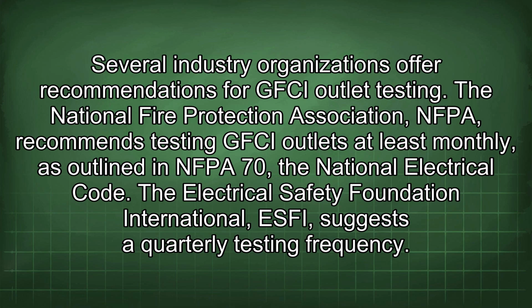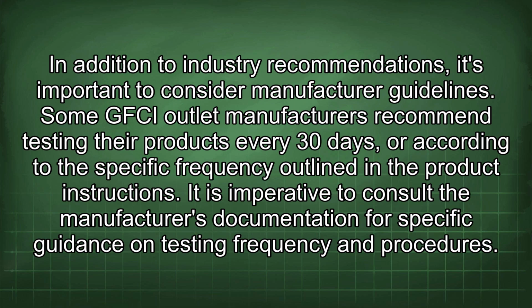The National Fire Protection Association (NFPA) recommends testing GFCI outlets at least monthly, as outlined in NFPA 70, the National Electrical Code. The Electrical Safety Foundation International (ESFI) suggests a quarterly testing frequency. In addition to industry recommendations, it's important to consider manufacturer guidelines. Some GFCI outlet manufacturers recommend testing their products every 30 days, or according to the specific frequency outlined in the product instructions. It is imperative to consult the manufacturer's documentation for specific guidance on testing frequency and procedures.